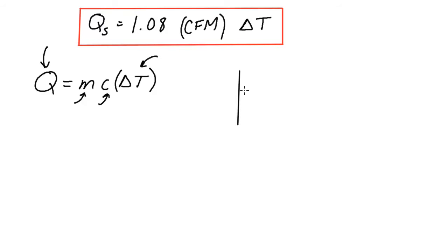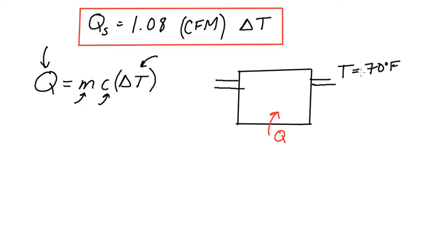So let's quickly just set up what is our typical problem as an HVAC engineer. We typically have a zone or a room that is receiving heat from inside or from outdoors, and we need this air to leave this room at a comfortable temperature, say 70 degrees Fahrenheit or around 21, 22 degrees centigrade. And we need to know what is the amount of mass and the temperature of the air that we've got to put into this space to absorb all the heat, so that when you add this heat, it results at this level. So we're typically dealing with moving air, and so we're not dealing with a static mass per se, we're dealing with a mass flow rate in our case, and we also are dealing with only air. And so we're going to rearrange some things and we're going to result in this formula.